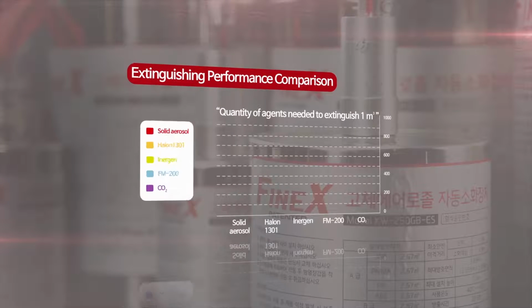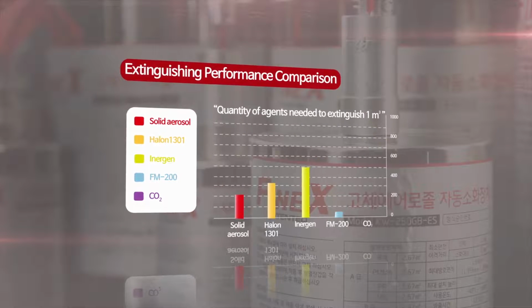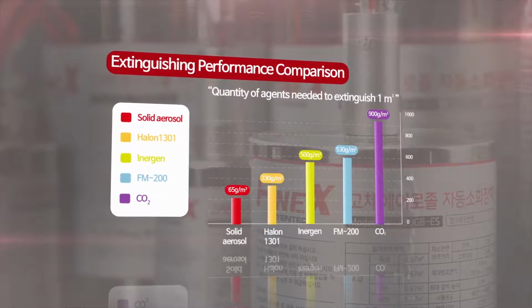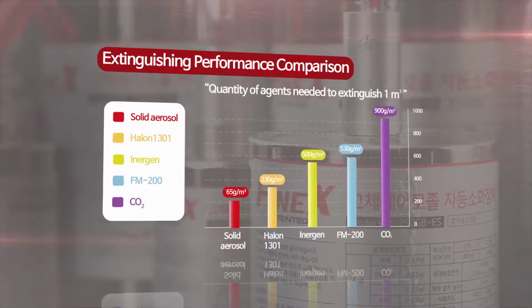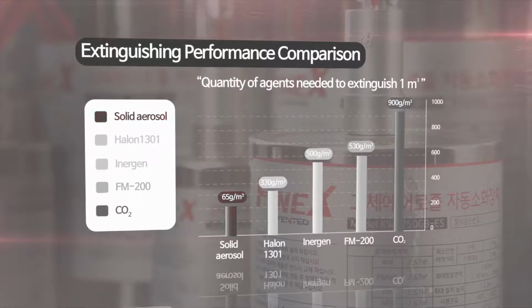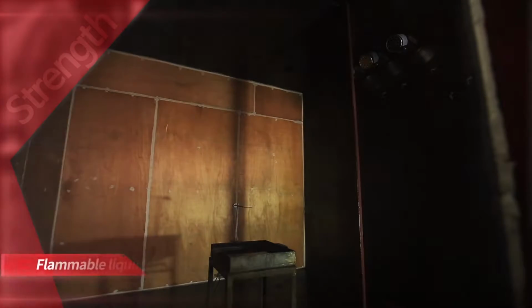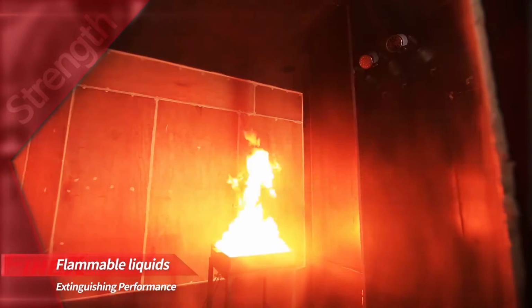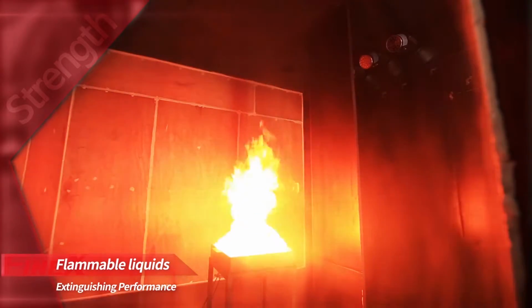FineX has a fire extinguishing concentration of 65 grams per cubic meter, which is much superior to halon 1301, with a concentration of 330 grams per cubic meter, and the lowest of all commercial fire extinguishing chemicals. In a laboratory of 34.72 cubic meters, N-heptane is ignited in a 50 by 50 centimeter pan. After the substance burns for 30 seconds, FineX begins operating, extinguishing the fire with 2.25 kilograms of chemicals.